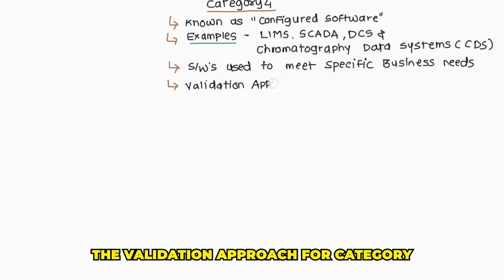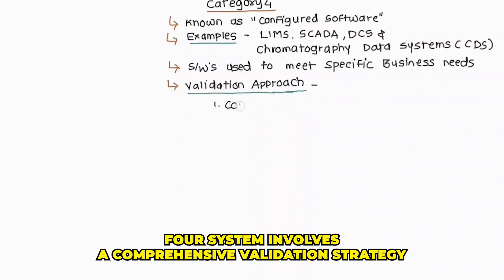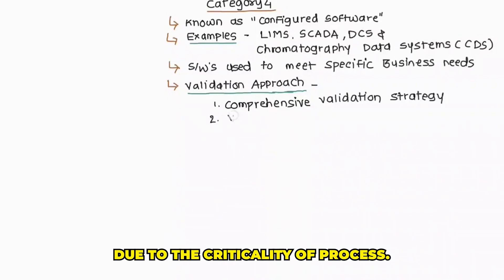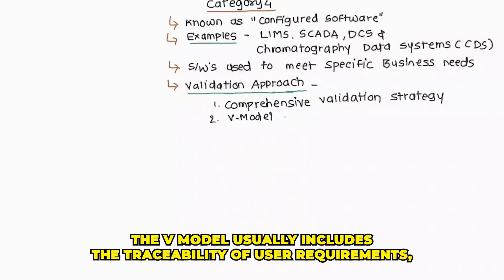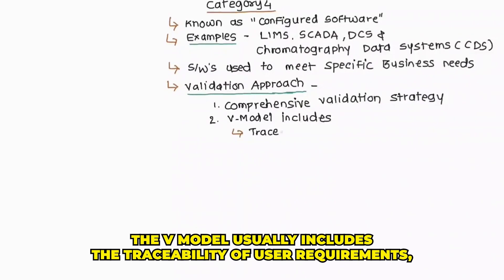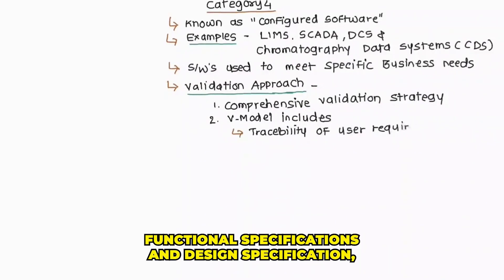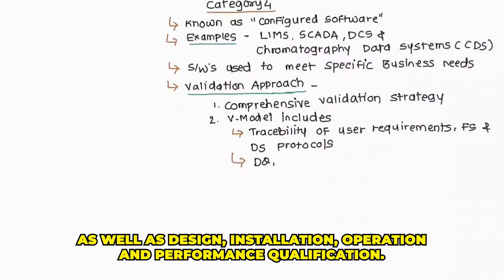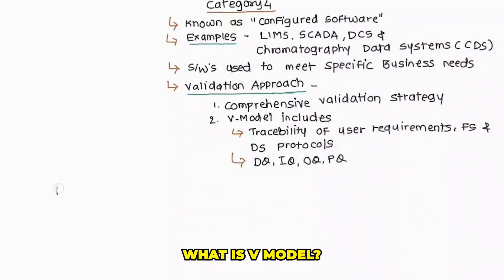The validation approach for category 4 systems involves a comprehensive validation strategy due to the criticality of processes they support. For this category, the V model usually includes the traceability of user requirements, functional specifications and design specifications, as well as design, installation, operation, and performance qualification. What is V model we will see in subsequent videos.